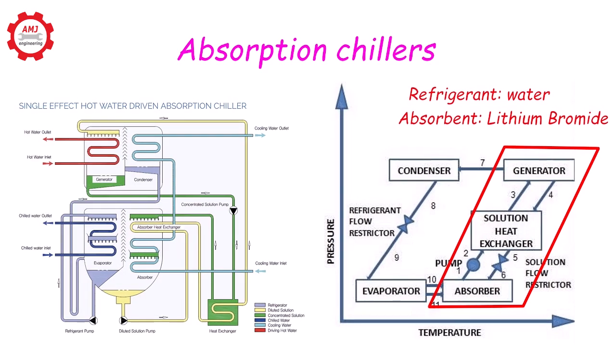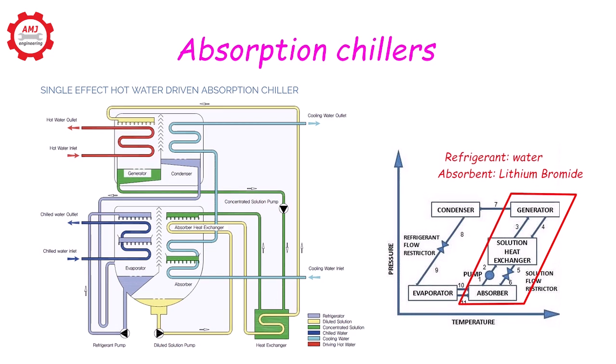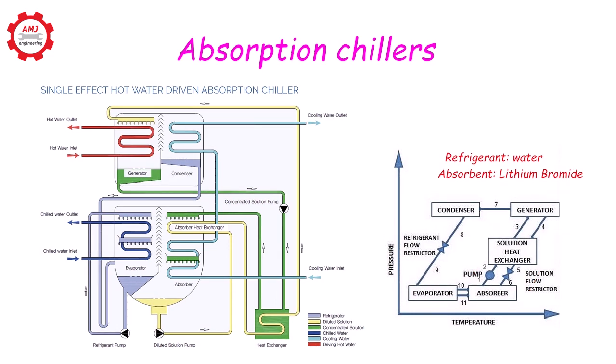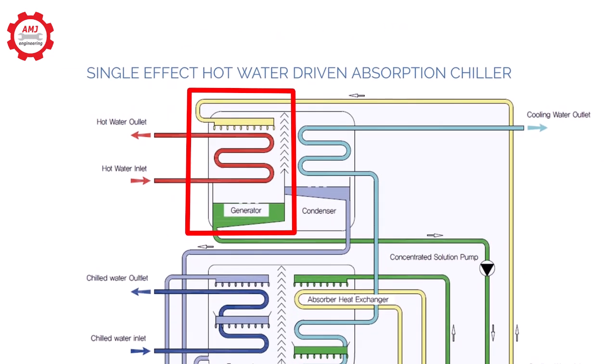The absorption cycle, illustrated here, can be summarized as follows. In the generator, gas, steam, or hot water is used to boil a solution of refrigerant-absorbent (water-lithium bromide). Refrigerant vapor is released and the absorbent solution is concentrated.